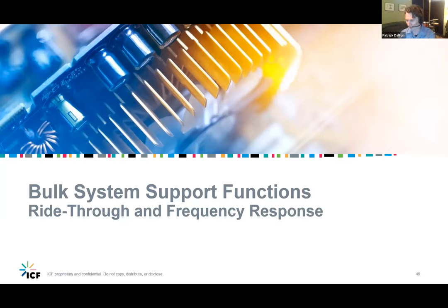There's another question regarding the functionalities, volt var, for example. When you have a DER with many inverters and a common PCC, do you consider that the functionalities are implemented in each inverter or in a centralized plant controller? Great question. That is sort of an underlying implication of the standard update and the requirement for having a RPA at the PCC: if there are multiple DER units, it's almost unavoidable that there is going to need to be some sort of plant controller. There have been discussions about that in the standards working group of, you know, we didn't explicitly say that plant controllers are going to be required. There might be other ways of meeting it.